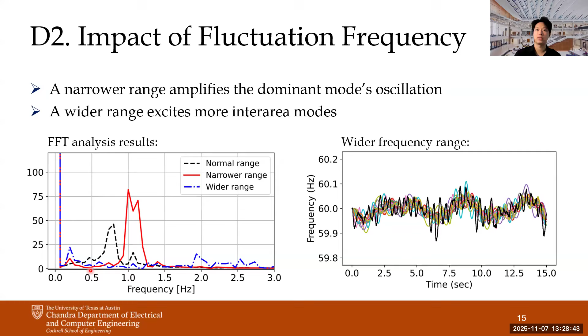However, as you can see from the right figure, in the wider frequency range cases, not only do we see the oscillation at 1 hertz, we can also observe lower frequency zones, around 0.2 to 0.3 hertz. So in these wider frequency scenarios, we should also think about the excitation of the inter-area mode from this data center demand.